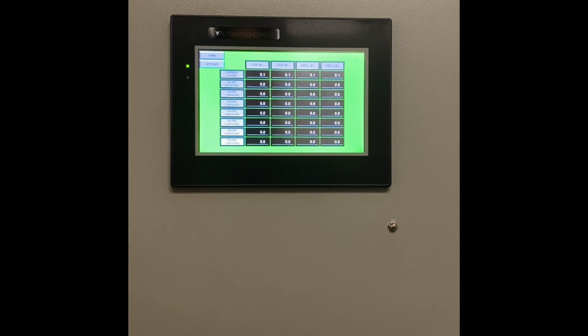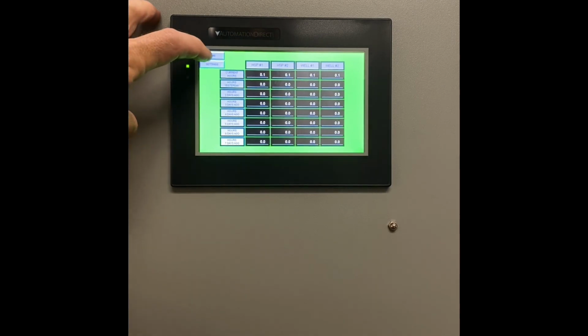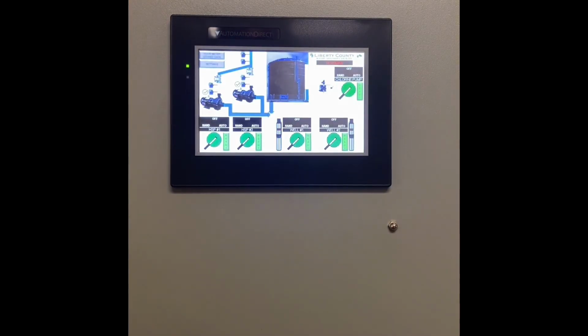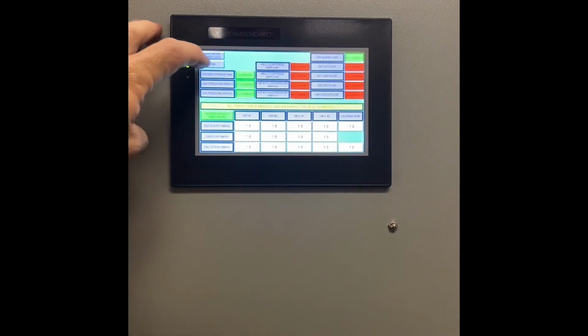This is very helpful for the operator because if he doesn't have to write the numbers down, generally they do not. So he can look back and go, oh, I see high service pump number 1 has been running twice as many hours as high service pump number 2. It will give you an indication of an impeller that's starting to wear out or some other issue that you're not aware of during your plant visit. Now I'll go back to the home screen, and now we'll go to the settings screen.